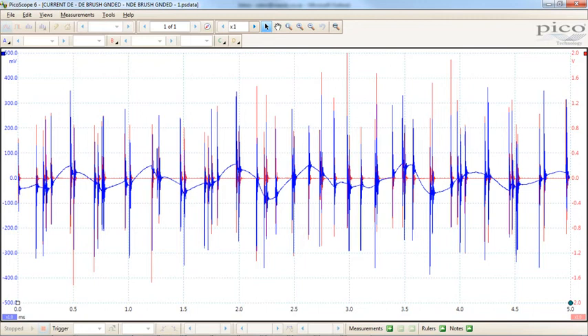This is the drive end brush with the non-drive end brush grounded. You can't see it here yet, but I'll show you another trace where you can actually see the common mode voltages. So you get the voltage build up, and then you get the current impulse for a while, then the voltage builds up again.